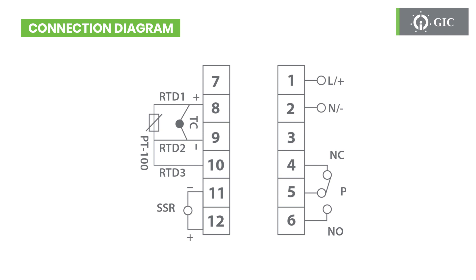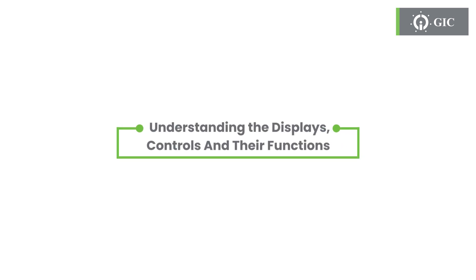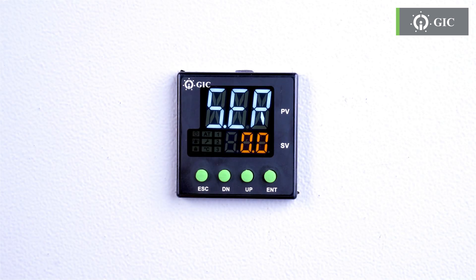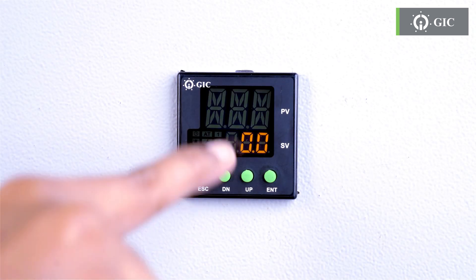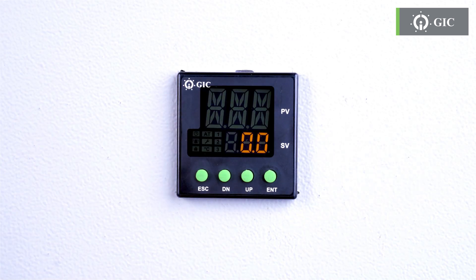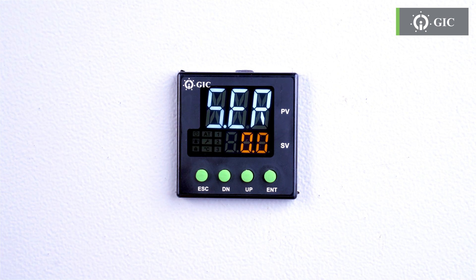Let's start by taking a look at the connection diagram. Before we get into programming, let's take a look at the buttons and their basic functionalities. Let's start with the two displays on the controller. The upper display shows the process value or PV — that is the current temperature of the process — while the lower display shows the set value or SV, which is the desired temperature set by the user.